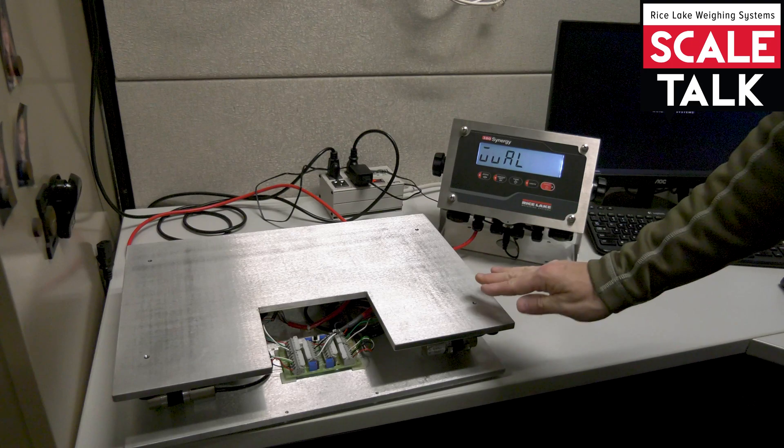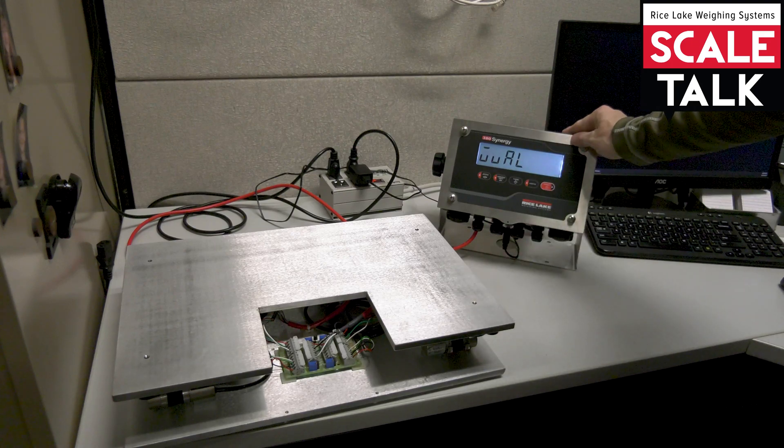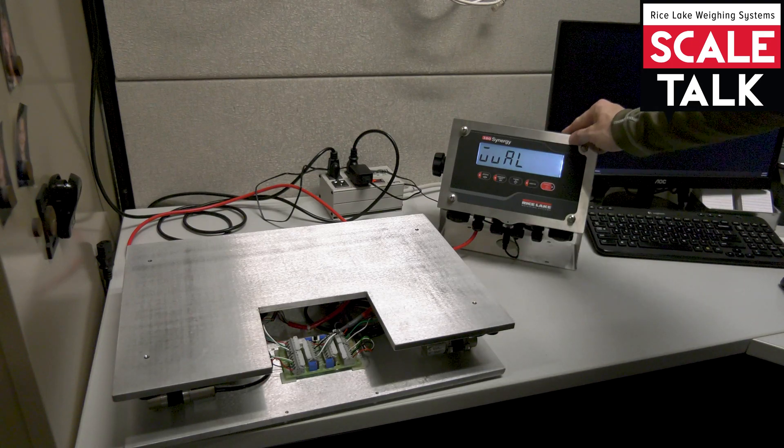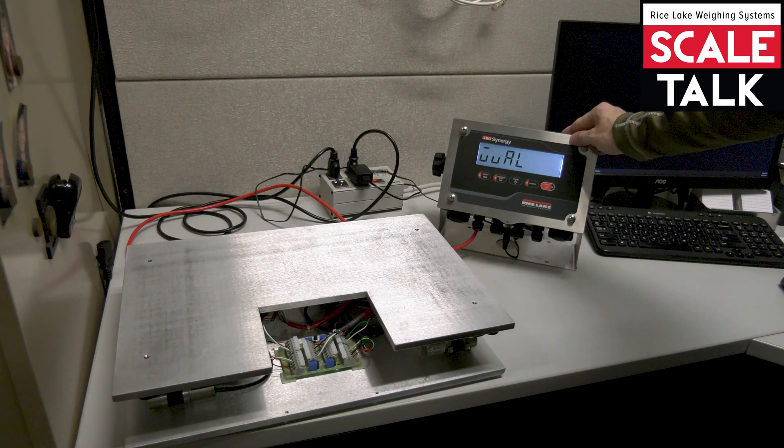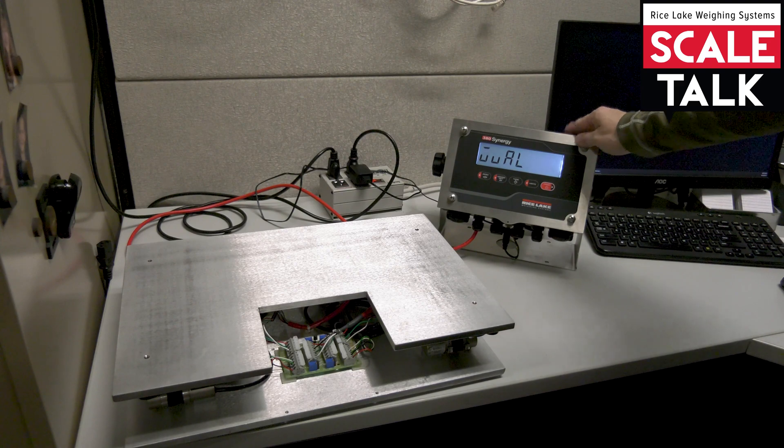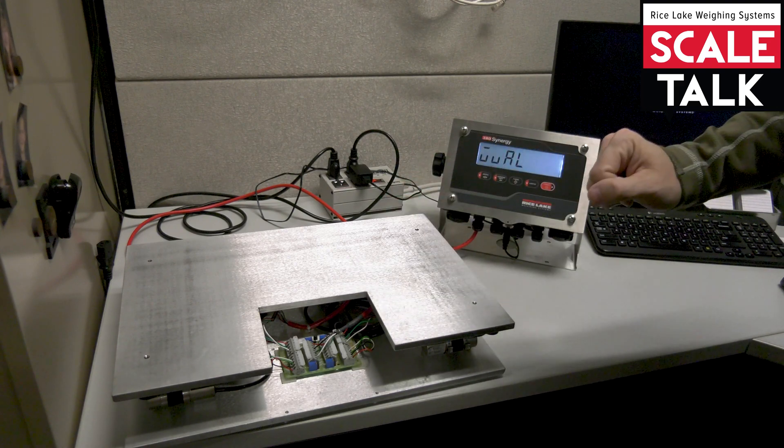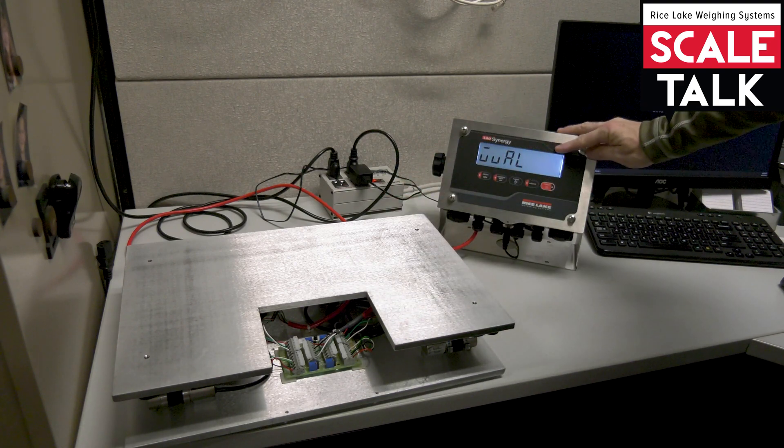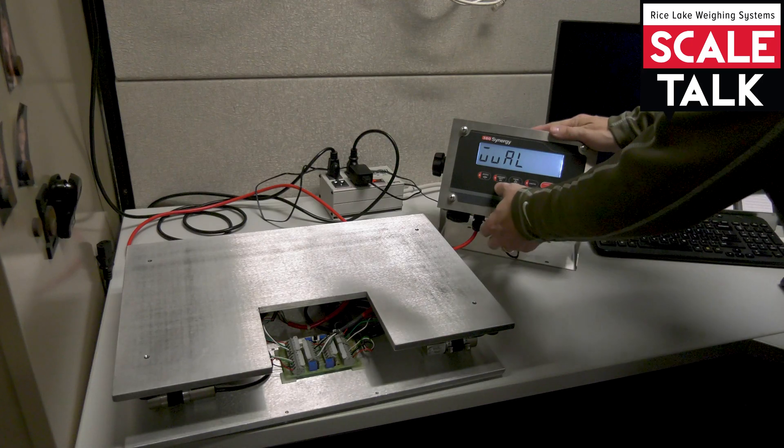So we just set this up to be a 50 pound scale. Handbook 44 would recommend that anything under 300 pounds should use full capacity for the calibration. So we're going to go ahead and put 50 pounds on the scale for that calibration. So we'll have to tell the indicator how much we're going to use. So let's come down.